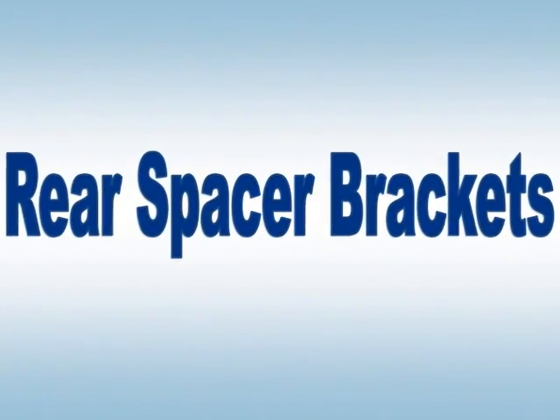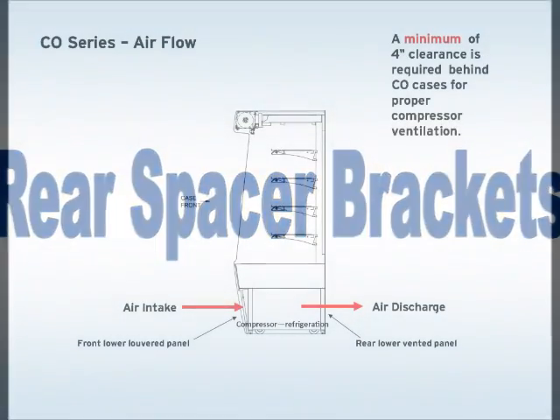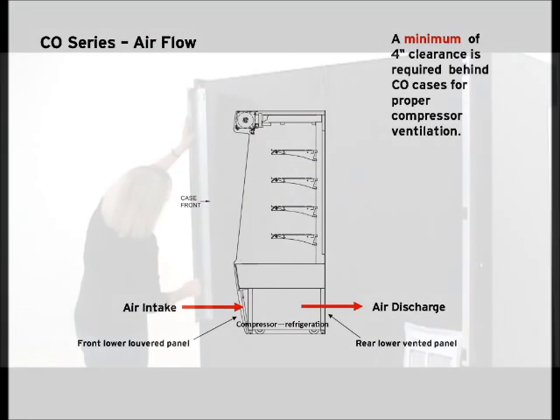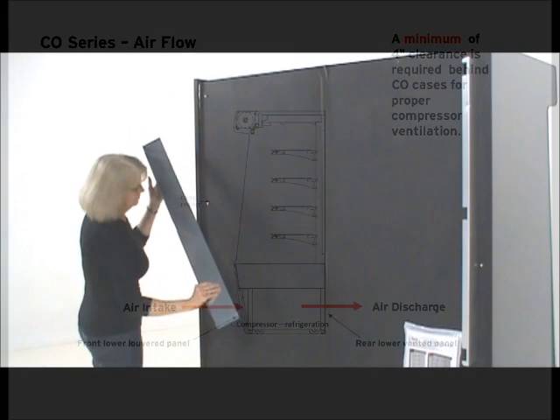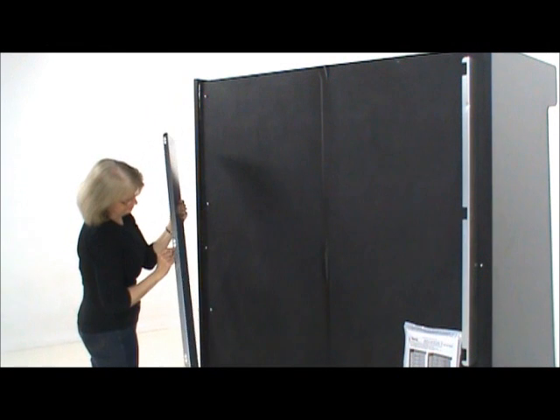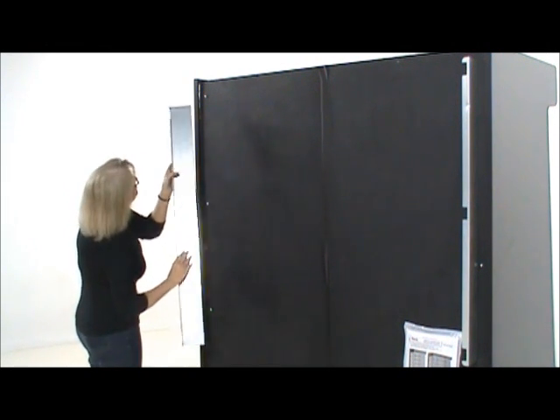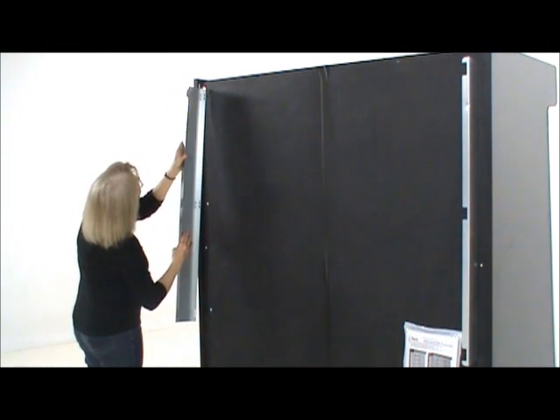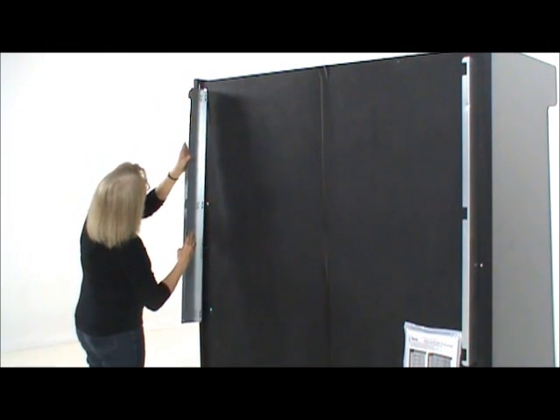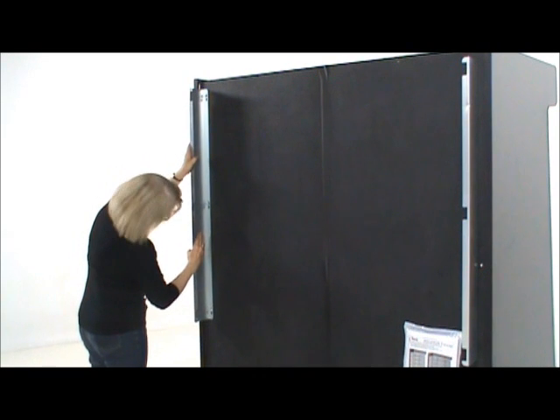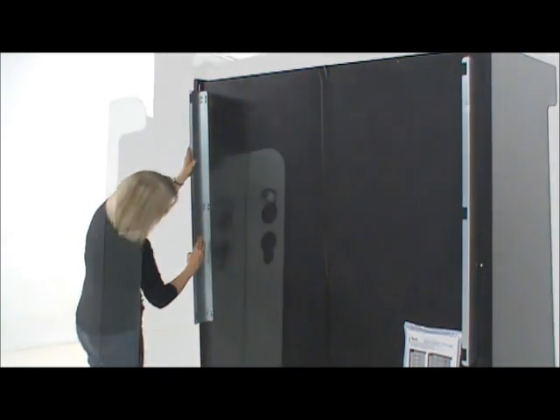Rear spacer brackets. CO models take air in through the lower front panel and discharge it out the rear of the case. To ensure adequate compressor ventilation, our CO models have a set of rear spacers. They are designed to keep the unit four inches from the wall.